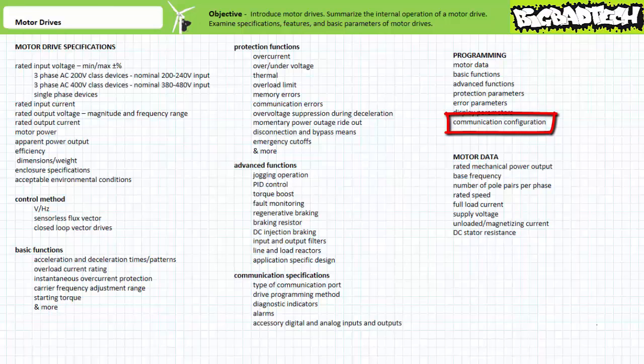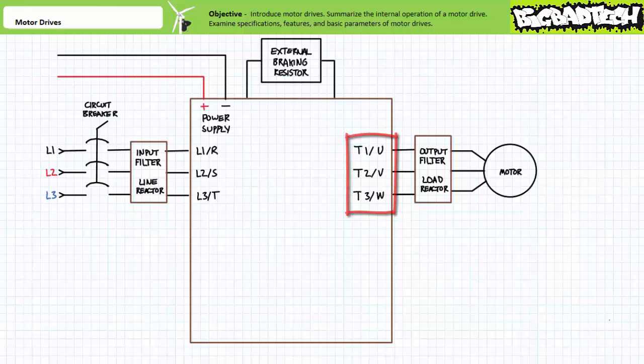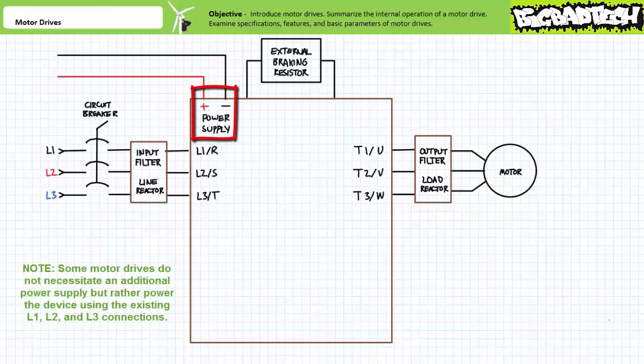A simplified block diagram of a generic motor drive intended to operate with three-phase AC includes three-phase AC input terminals specified L1, L2, and L3 (or sometimes R, S, and T depending upon country of origin), and three-phase output terminals specified T1, T2, and T3 (or sometimes U, V, and W). Between the three-phase AC input, one might observe external disconnection means like a circuit breaker, as well as any accessory external input filters or line reactors. Between the three-phase AC output and the motor, one might observe any accessory external output filters or load reactors. A motor drive also necessitates an external power supply connection to power up the internal electronics.